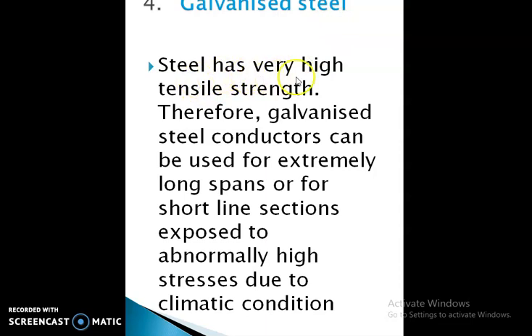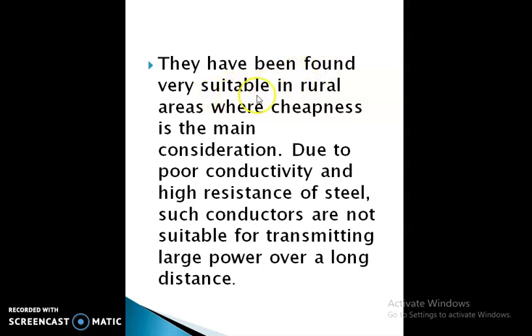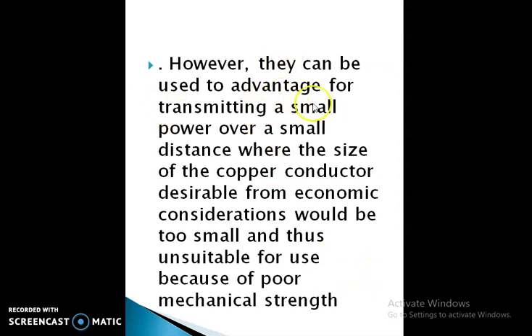The next type is galvanized steel. Steel has very high tensile strength, therefore galvanized steel conductors can be used for extremely long spans or for short line sections exposed to abnormally high stress due to climatic conditions. They have been found very suitable in rural areas where cheapness is the main consideration. However, due to poor conductivity and high resistance of steel, such conductors are not suitable for transmitting large power over a long distance. They can be used to advantage for transmitting small power over short distances where a small copper conductor would be mechanically unsuitable.